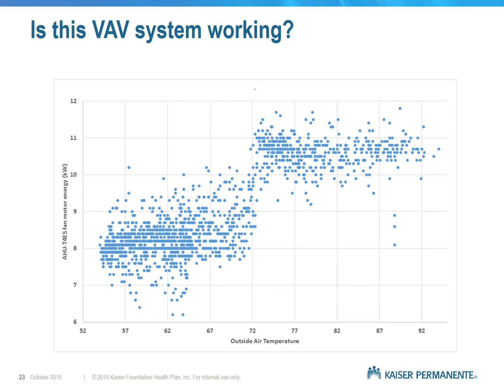So let's connect the dots. And yes, connect the dots, pun intended. No matter what energy modeling software you use, they all output energy into buckets: fan energy, cooling energy, heating energy, etc. And they can all output the model into an 8,760 line spreadsheet representing the design year. So you can easily take that output and plot, let's say, fan power versus outside air temperature in the design year, and you'll get a chart that looks like this. Once you have that, you can pretty easily draw a line like this that captures 95% of the data. In other words, only 5% of the points in the design year fall above this line.